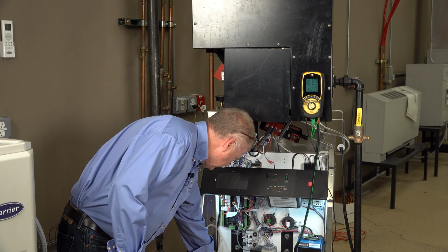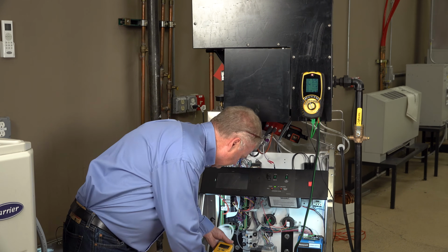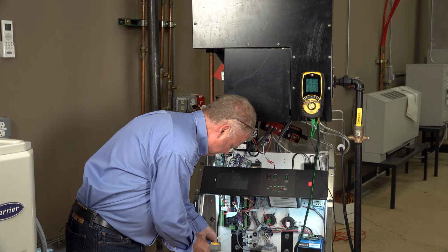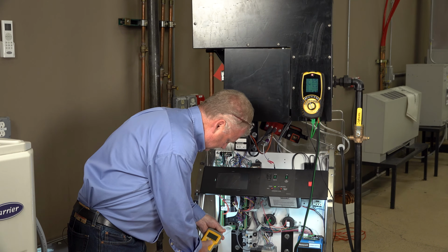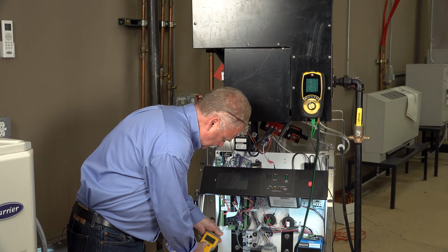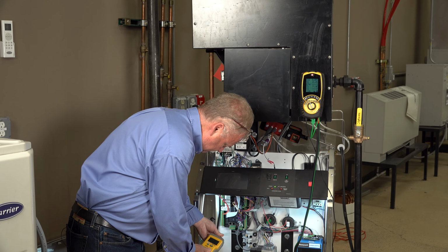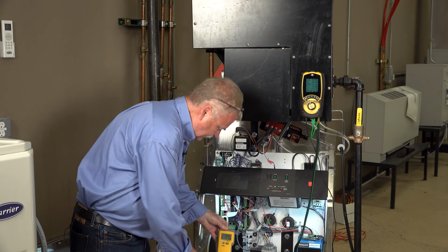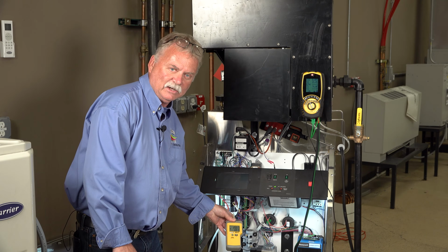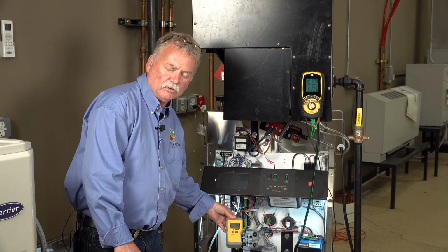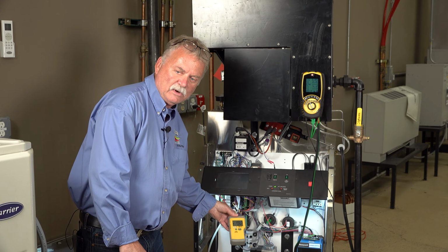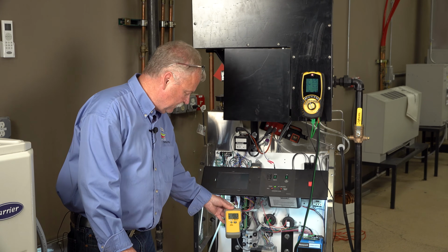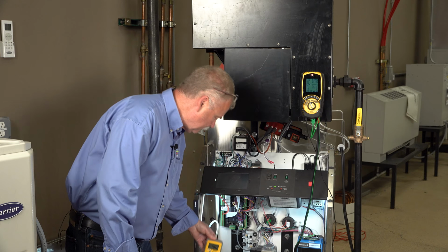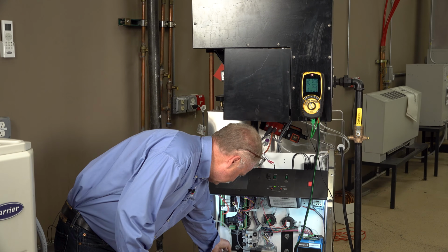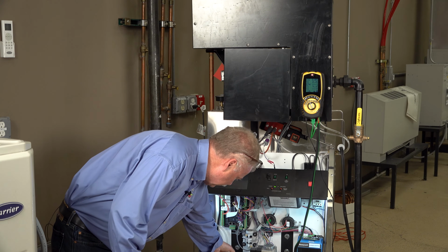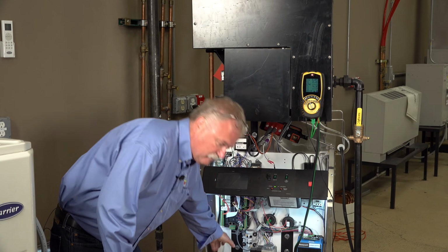If we look at our meter now, I have to zero it out again. What we're seeing is we have 7.76 inches coming in. Like I said, I was looking for anywhere from 3 to 12, with 7 to 8 being ideal. So we're right in that ideal range.